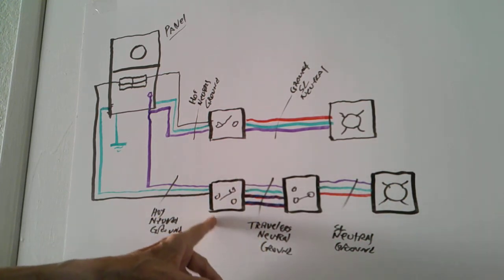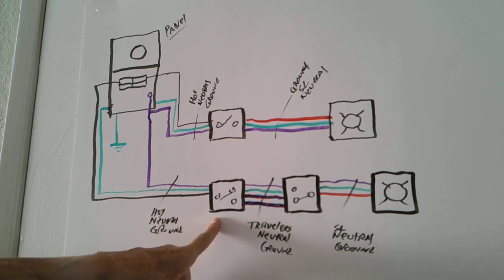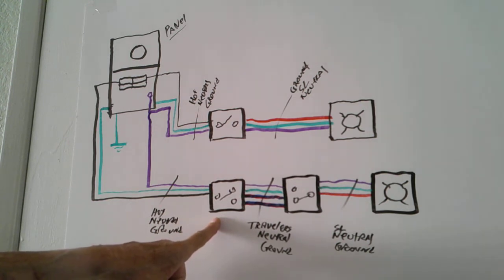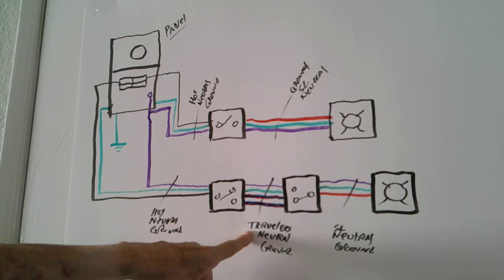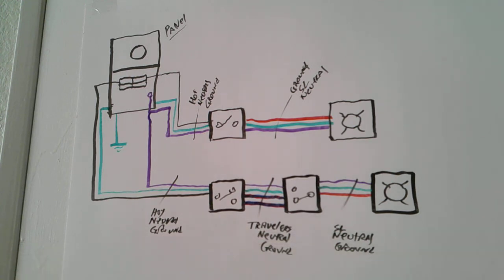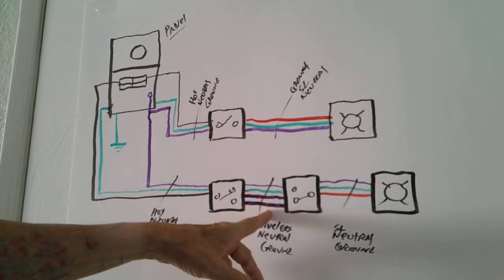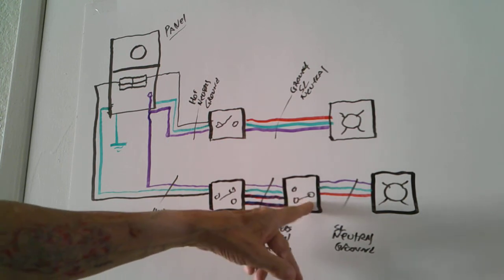On a three-way switch here, you will have a black screw and two brass screws. Okay? The black screw is designed to be the hot or the switch leg. The two brass screws are designed to be the travelers. Oftentimes people miswire them or incorrectly wire them, and then they have all kinds of problems. Now, you want to check this group of wires here by checking this switch.